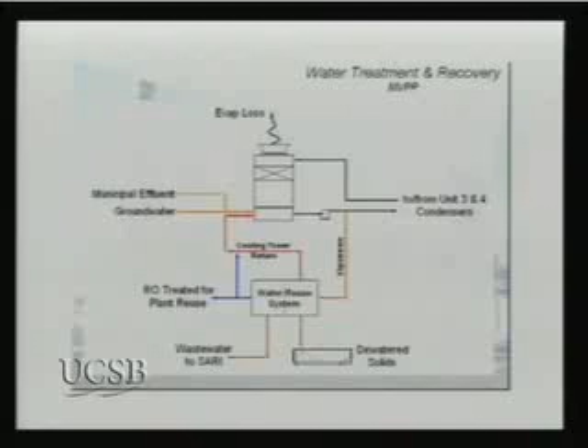Okay, this is an overview of the plant, of how the system's put together. It's got a reactor clarifier, sometimes known as a solids contact clarifier, a softener. This basically takes out calcium, magnesium. It ends up making a slurry-looking stream, which is thickened, and that is just a dry sludge cake that is hauled all the way to the middle of California to Buttonwillow for disposal. That's because it has perchlorates in the solids material. From there we go to gravity filters. A portion of that goes straight to the cooling towers.